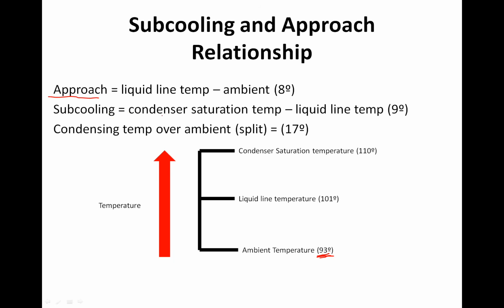Subcooling is the condenser saturation temperature minus the liquid line temperature. Here, our condenser saturation is 110, our liquid line temperature is 101. 110 minus 101 is 9 degrees of subcooling. And we talk about condensing temperature over ambient. It means how much higher our condenser temp is than our ambient temp. Here our condensing temp is 110 and our ambient temp is 93, so there's 17 degrees difference. The saturation temperature of the refrigerant is 17 degrees above the ambient temperature.